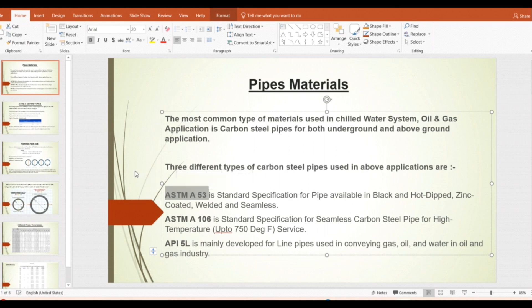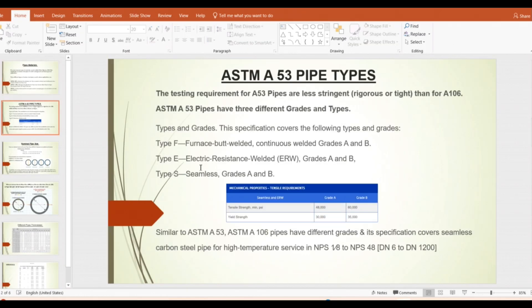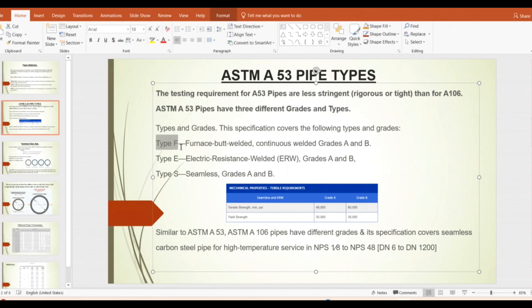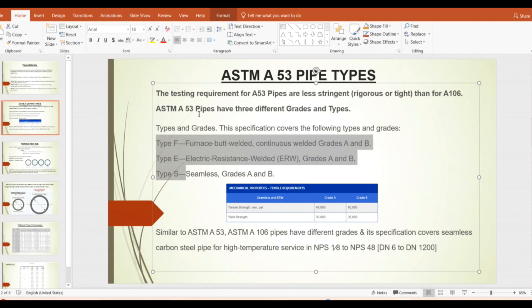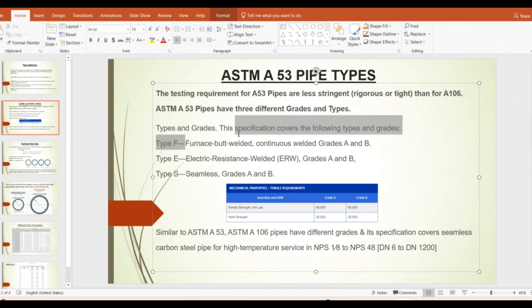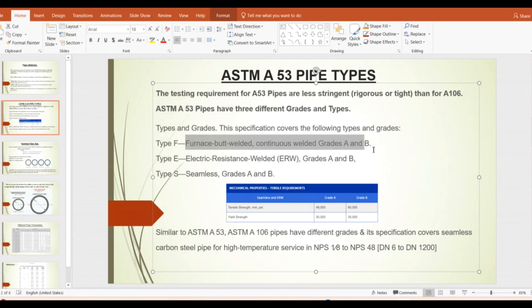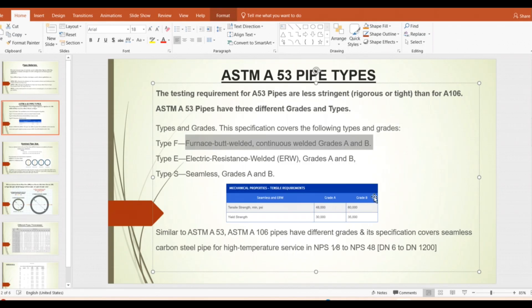That is why we normally use ASTM A53 pipes. Looking at the types and grades: for ASTM A53 pipe we have Type F (furnace butt welded), Type E (ERW welded), and Type S (seamless). Each type can be Grade A or Grade B. Each grade has different tensile strength and yield strength — for example, Grade B has higher tensile strength and higher yield strength.